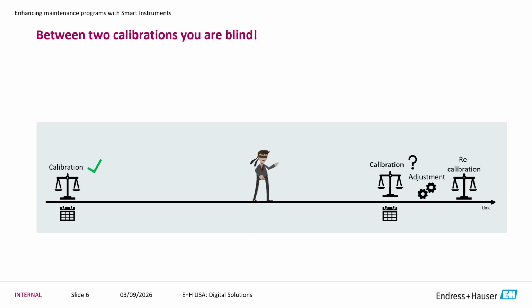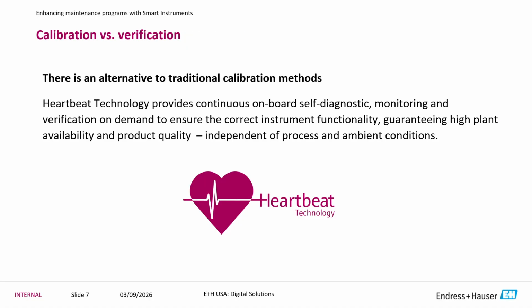I hope it's right? And if it does go out of tolerance, you don't know if that happened on day 2 or day 364. You're completely blind. And if it does become out of tolerance, when did it actually become out of tolerance? That investigation is a lot harder to do, because you have 12 months of no data. So we've introduced some technologies.